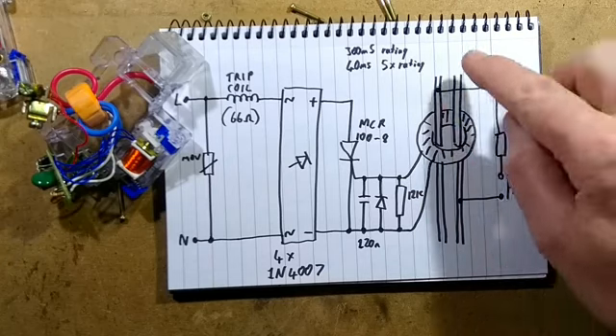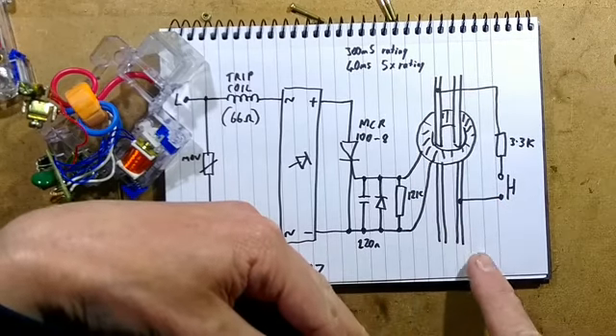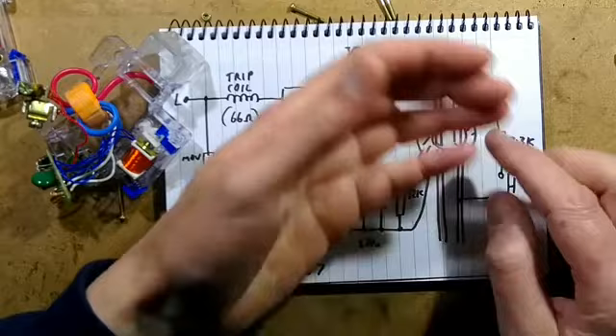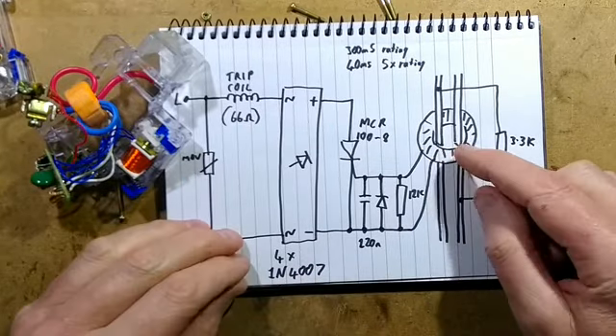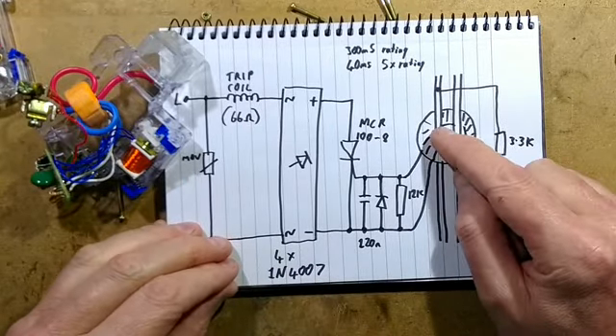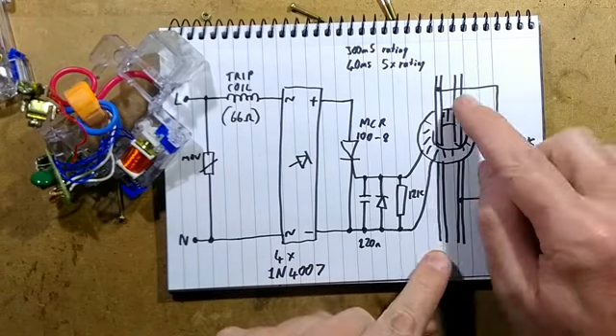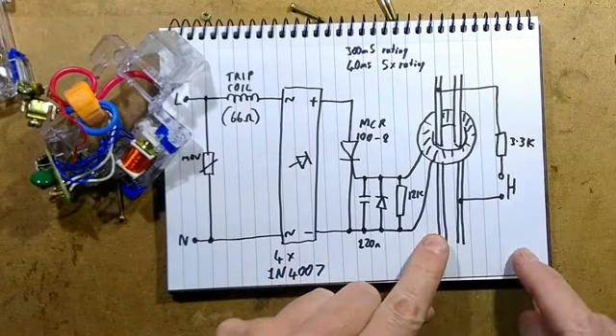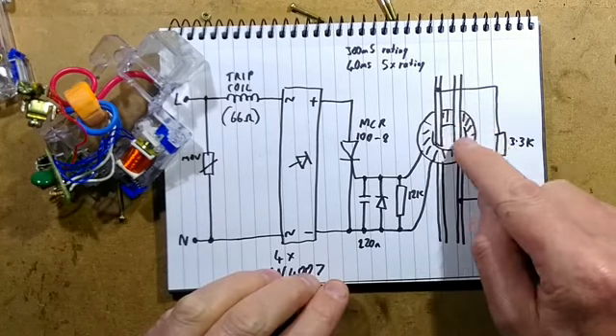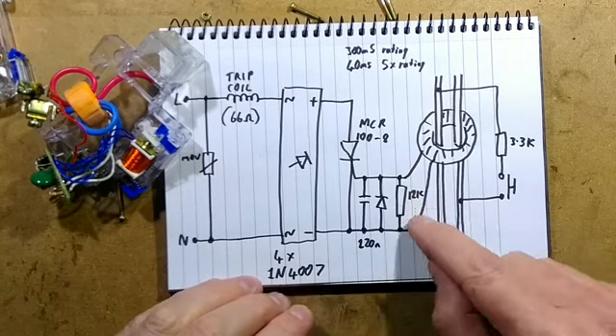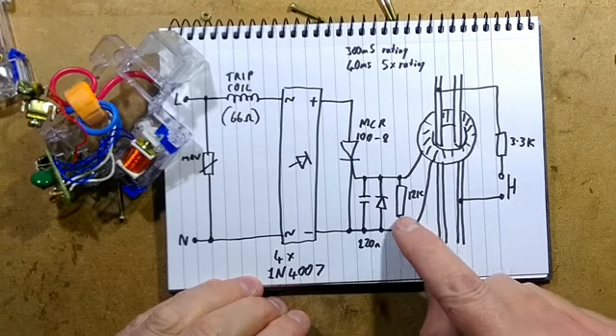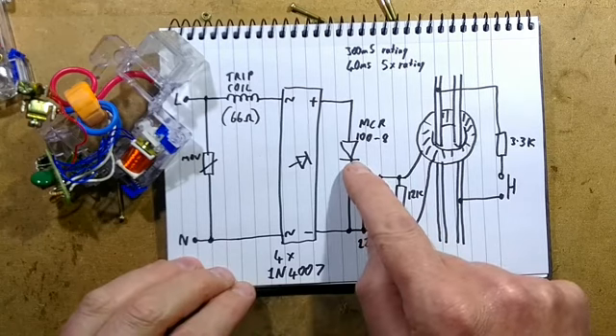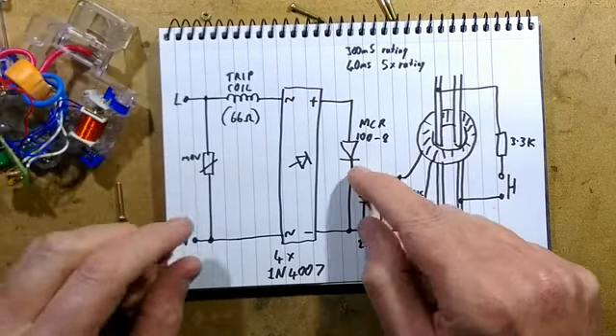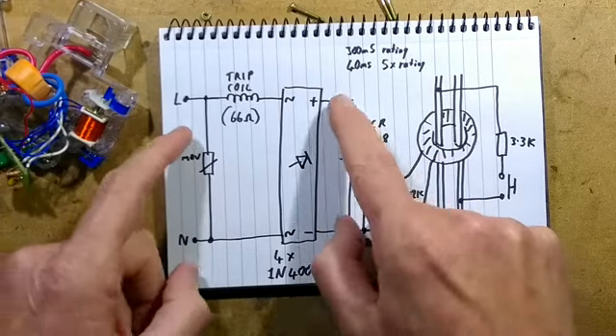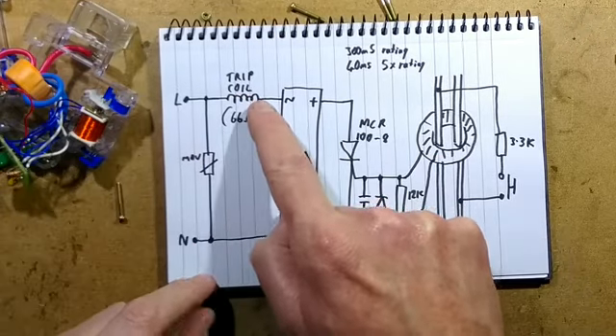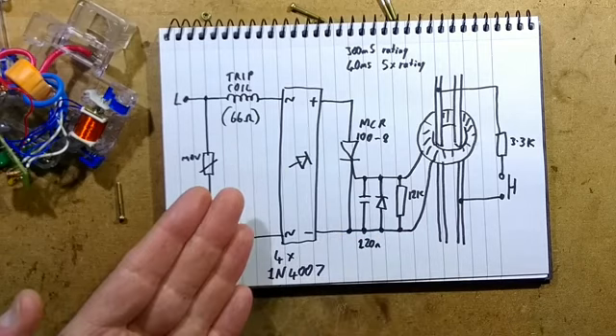But basically speaking, you've got the current flowing out through this wire and coming back through this wire. And if they're balanced, if it's the same amount of current, nothing will be induced in this magnetic core. But if something leaks to ground, so it's coming in through live, some of it's leaking to ground and not all of it's going back, you'll get an imbalance which will create a small voltage here. And after a very tiny delay, it'll trigger this thyristor. The thyristor will turn on, and it latches on, and will effectively shunt the supply rails, which will energize the trip coil and then kill the circuit.